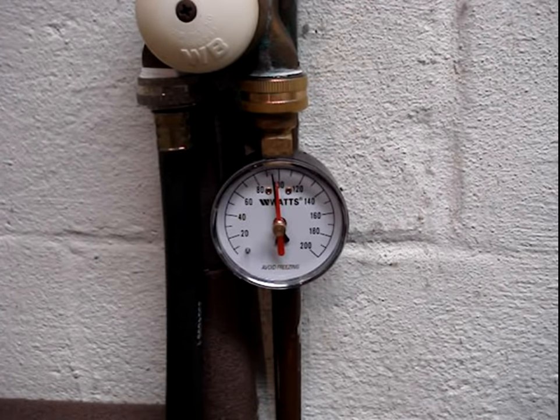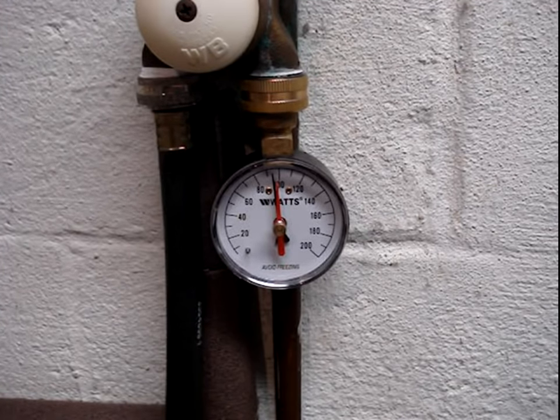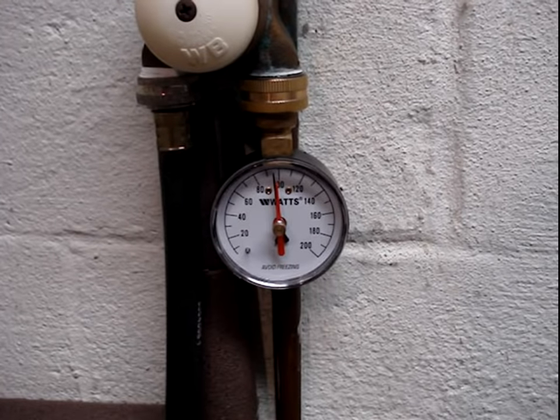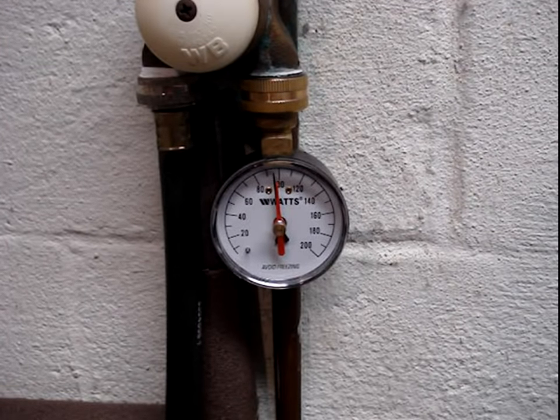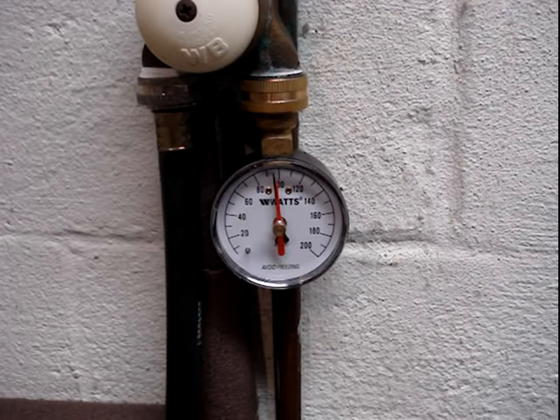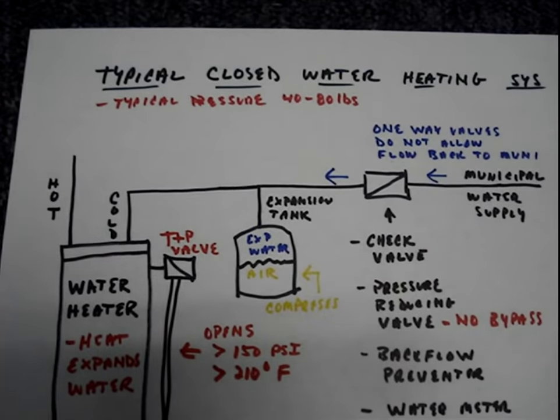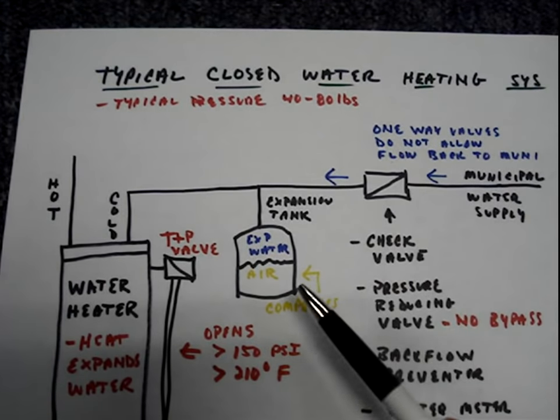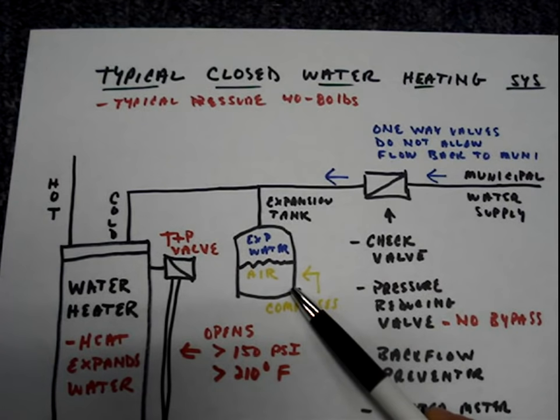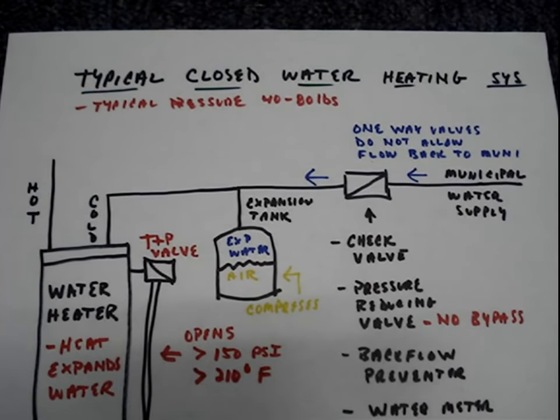If the pressure on this open system increased to 150 pounds and opened the temperature and pressure valve, then odds are good that the bypass on the pressure reducing valve has not opened. If 150 pounds is reached on a closed system, then it's likely that the bladder in the expansion tank has failed and it's filled with water. If the system passes the thermal expansion test, then the last thing to check is that the water heater is not heating water over the 210 degree Fahrenheit limit.